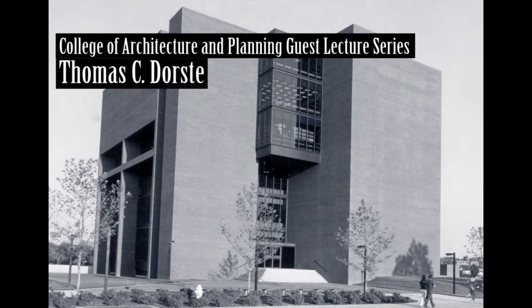We did the studies. Not one of them was feasible, simply because the information that was available from the manufacturers was so vague that there was no way we could come up with any figures. They were new pieces of equipment. They were high efficiency, reflectors behind them, sealed tube type collectors. Nobody knew exactly what their operating characteristics were. Nobody knew exactly what they were going to cost. So we investigated on our own a Lennox flat plate collector that's been on the market for years, which turned out to be feasible. In that case, they can return their investment without capitalization in 12 years, and as far as they're concerned, that's good enough. So that's designed in the building and will be built as part of the building when it's bid in about 3 weeks.